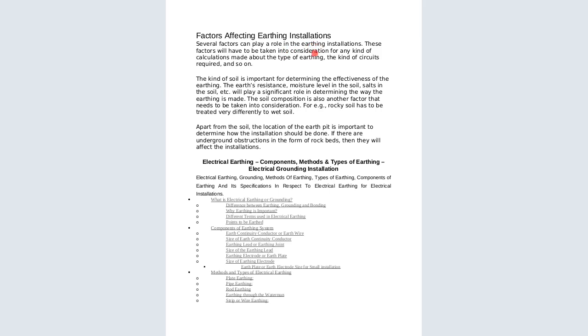So there are factors that affect earthing installation. Several factors can play a role in the earthing installation. These factors will have to be taken into consideration for any calculation made about the type of earthing, the kind of circuits required and so on. The kind of soil is also important to determine the effectiveness of earthing. The earthing resistance, the moisture level in the soil, salts in the soil, etc., will play a significant role in determining the way the earthing is made. The soil composition is another factor that needs to be taken into consideration. For example, rocky soil has to be treated very differently from wet soil. Apart from the soil, the location of the earth pit is important to determine how the installation should be done. If there are underground obstructions in the form of rock beds, then they will affect the installation.